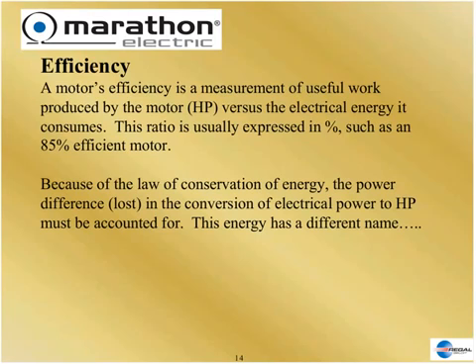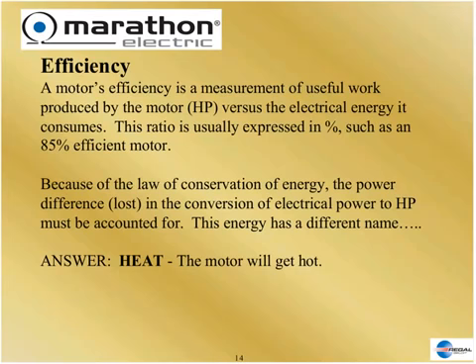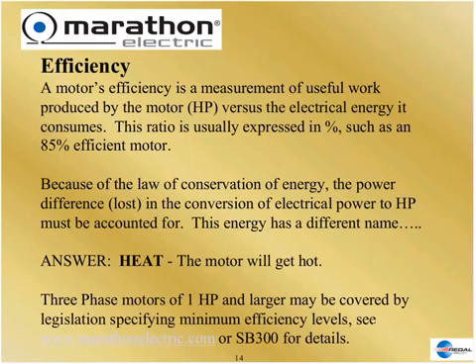There is no possible way, unless you defy the laws of physics, to make the horsepower output exactly equal to the input supplied by the utility — there's always some loss. The loss is expressed as efficiency: the ratio between the work done and the work in, expressed as a percent. Because of the laws of conservation of energy, if we're not converting 100% of energy into motor horsepower, we're converting it into heat. When a motor does work, just like you and I, it will get hot.